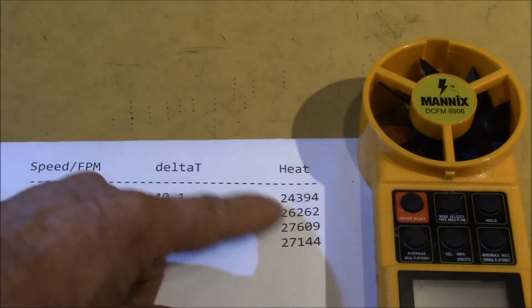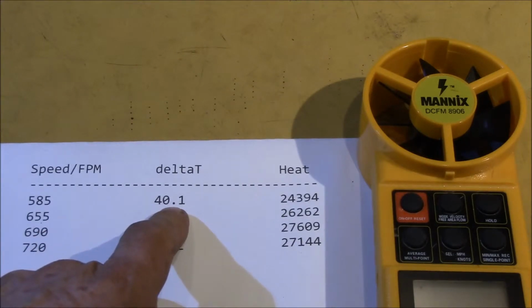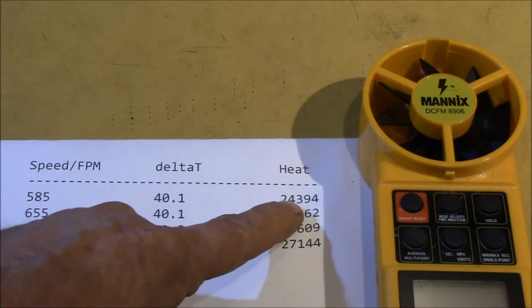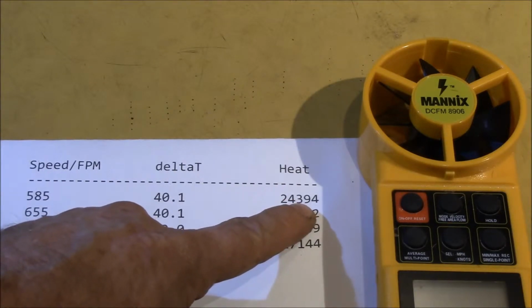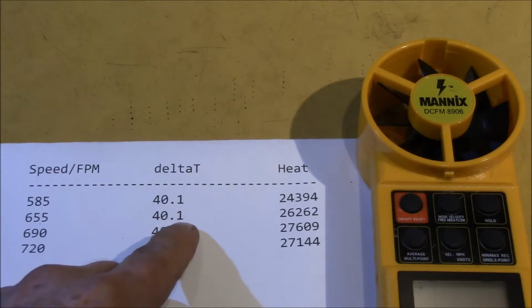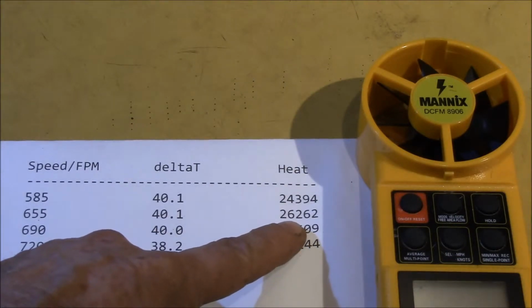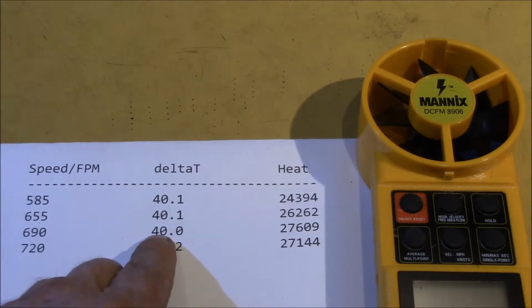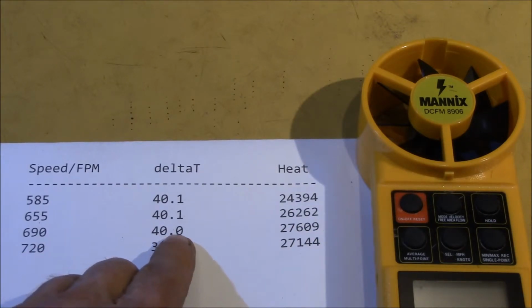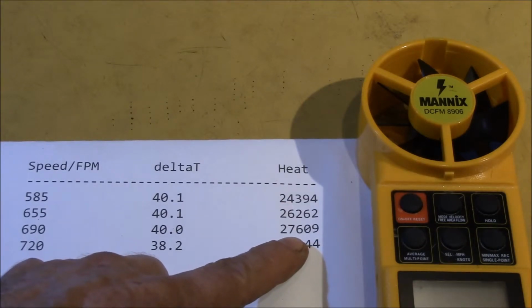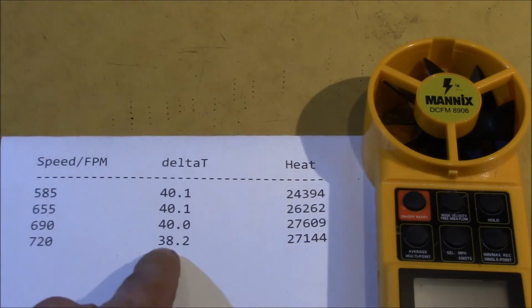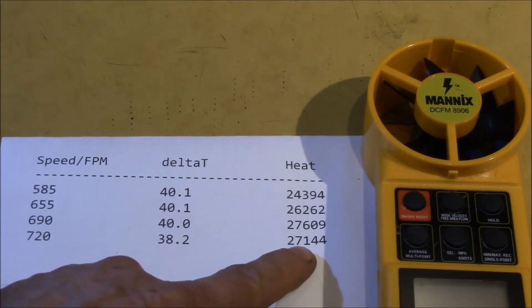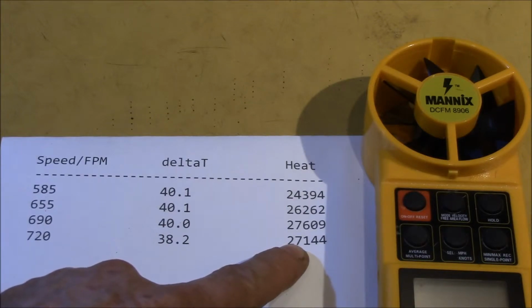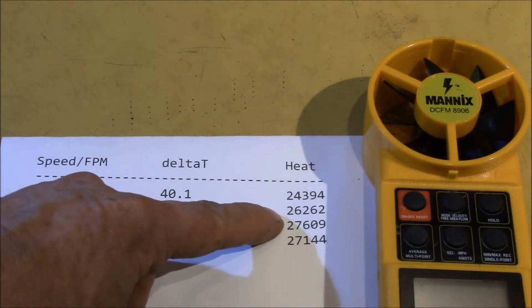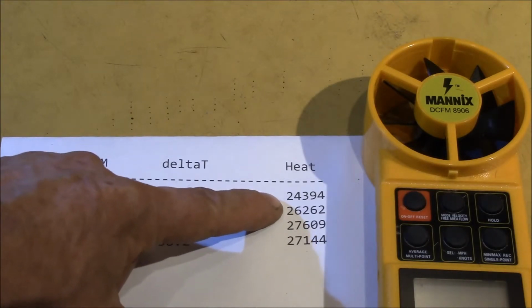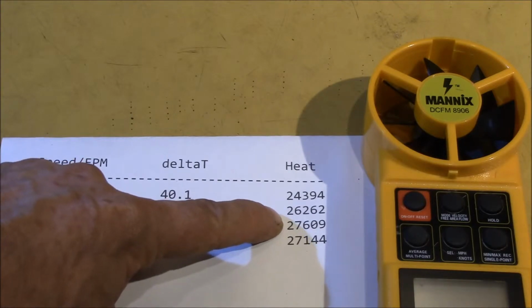At the slowest speed setting, I had the highest incoming temperature, but I was only getting 24,394. When I sped it up, I still got a pretty good temperature, about 26,000. If I sped it up a little more, where I started dropping the temperature, I got 27.6K, and at full speed the temperature drops even more, down to 27.1. So my sweet spot is kind of right about here - I thought it was here before, but looks like I have to go a little higher.